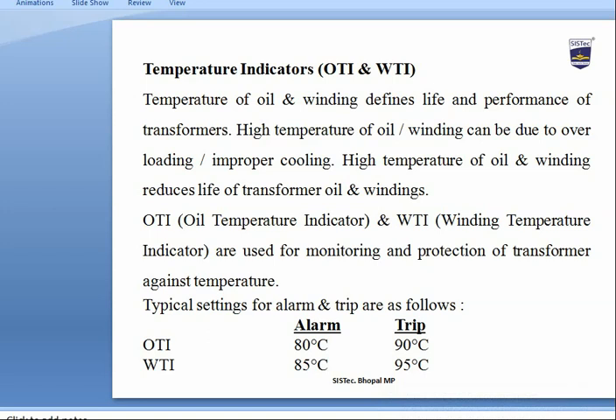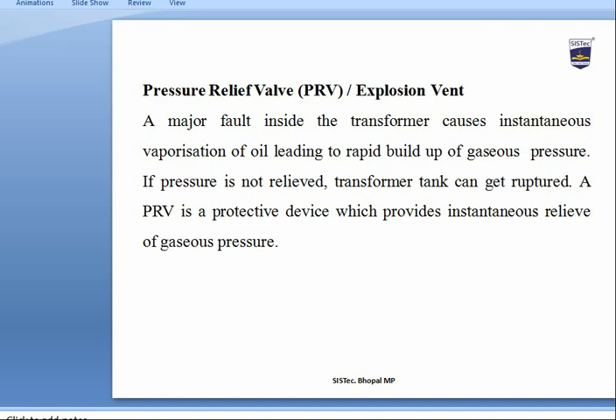As long as temperature is below 80°C, the transformer operates normally; at 80°C the alarm signals abnormal performance; at 90°C the transformer is tripped. For WTI, an alarm is raised at 85°C and a trip occurs at 95°C.